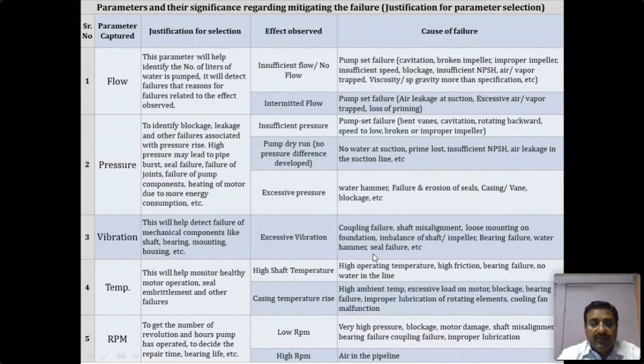If I think about vibrations, then yes, excessive vibration is one of the effects observed. What are the different causes? The coupling failure, shaft misalignment, loose mounting on the foundation, imbalance of the shaft, impeller, bearing failure, water hammer, seal failure. So we have identified many different causes for every single parameter variation. Okay. So if the parameters show abnormal variation, then what are the different causes for those variations? Those have been captured and shown in this slide. Is it fine? Shall we move ahead?